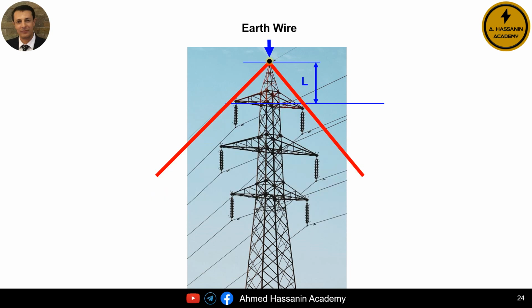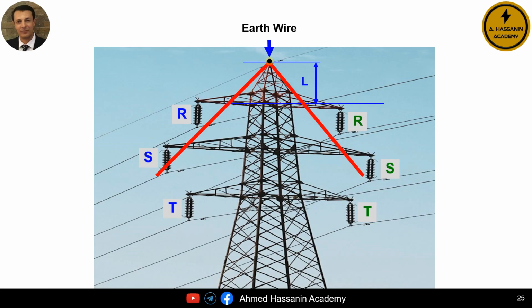So, we have understood that this tower is designed for a certain voltage level, and the earth wire, also called shield wire or ground wire, is installed at a specific height, thus providing a certain protection angle. Let us assume that the tower in front of us has the same voltage level as the previous tower, but it was designed for certain technical reasons requiring, for example, a specific horizontal spacing between the phase conductors. Suppose the earth wire, also called shield wire or ground wire, is installed at the same height as before, and since the height is the same, the protection angle remains the same.